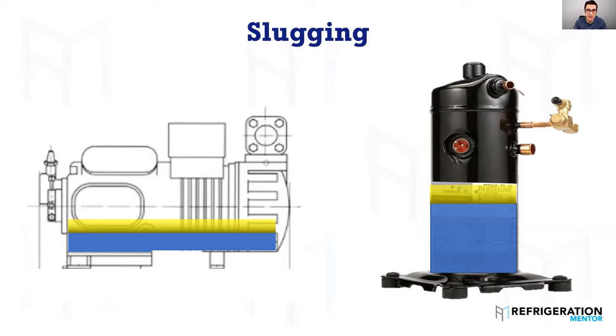So that's three different ways slugging can happen, and each one happens differently. This is really important to understand because you need to know exactly what type of slug the compressor took. A slug is a slug — but was it a slug from oil? Was it an air-cooled compressor? Was it a refrigerant-cooled compressor? Understanding the different ways compressors take a slug is going to make your job easier to troubleshoot, repair, and fix those issues so it doesn't happen again.